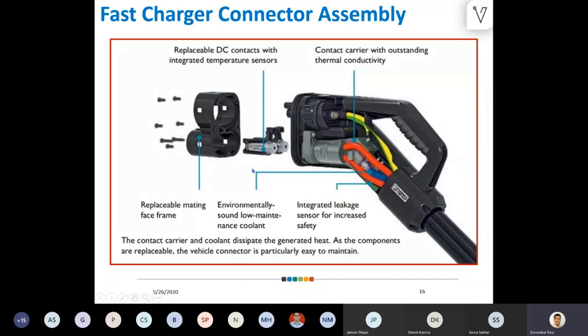It also has a temperature sensor inside to make sure the connection is proper, the contact is made properly, and contact resistance is as low as possible. This also ensures the connector doesn't heat up too much so the connection pins or connector itself don't start burning due to very high temperature. That's why the temperature sensor is installed inbuilt in the DC contacts.